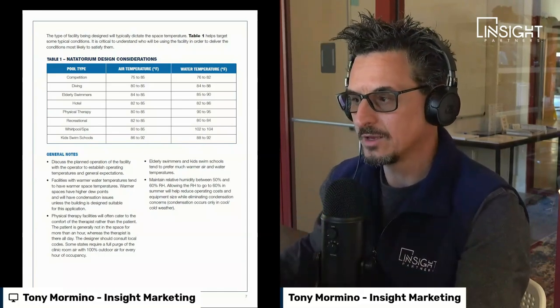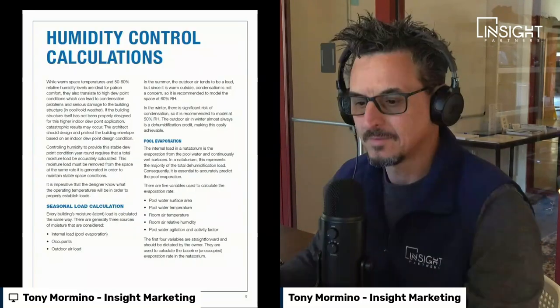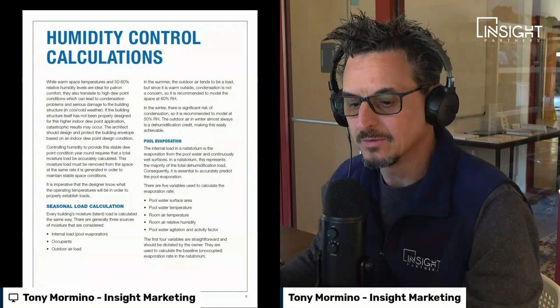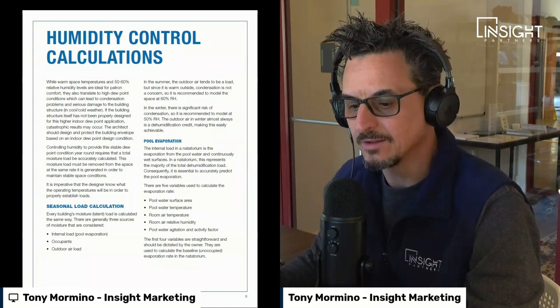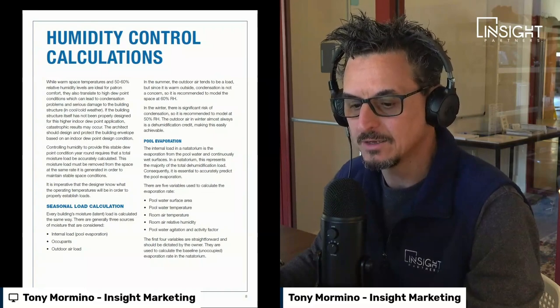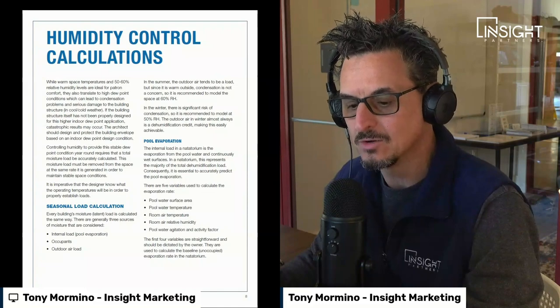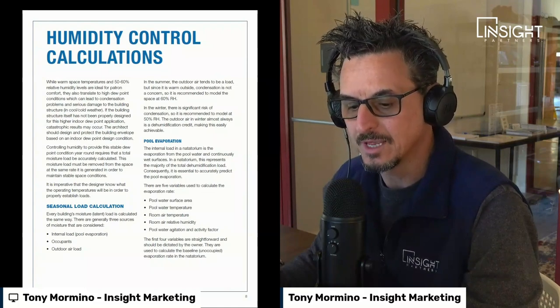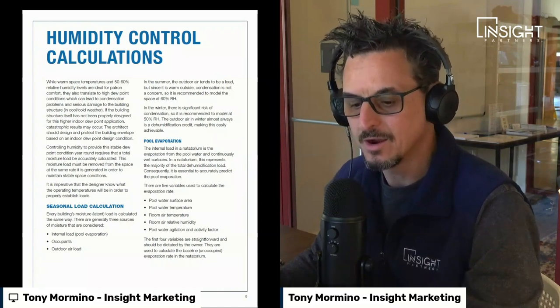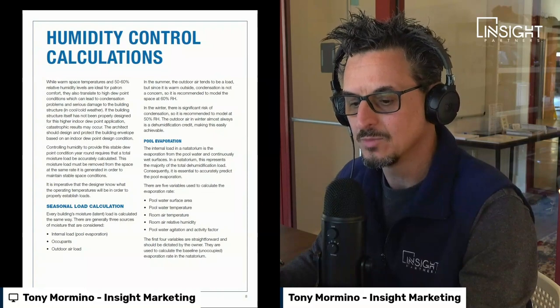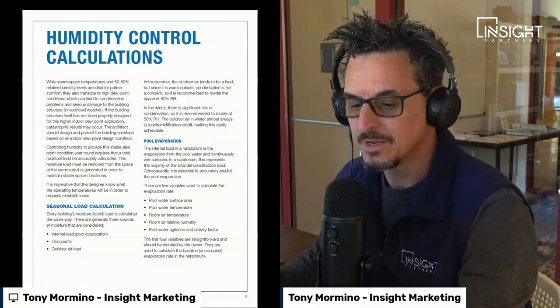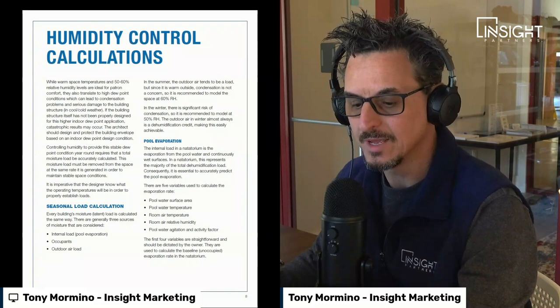Moving on to humidity control calculations. While warm space temperatures and 50–60% relative humidity levels are ideal for patron comfort, they also translate to high dew point conditions, which can lead to condensation problems and serious damage to the building structure in cold weather. If the building structure has not been properly designed for this higher indoor dew point application, catastrophic results may occur. Controlling humidity to provide a stable dew point condition year-round requires that a total moisture load be accurately calculated — this moisture load must be removed from the space at the same rate it is generated.